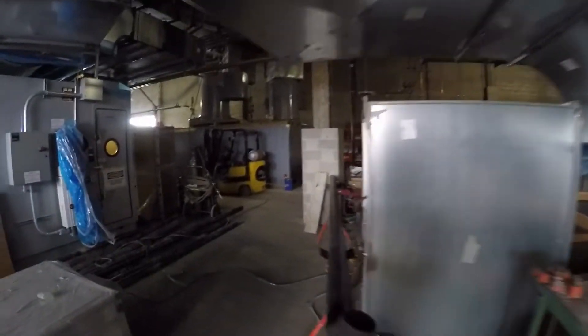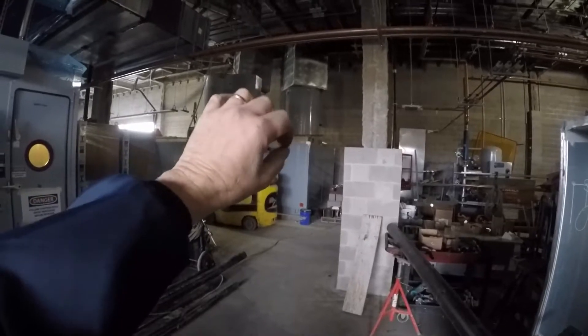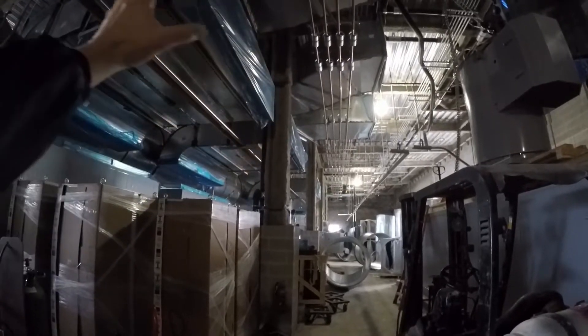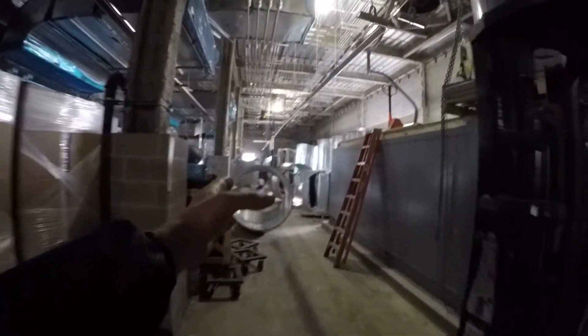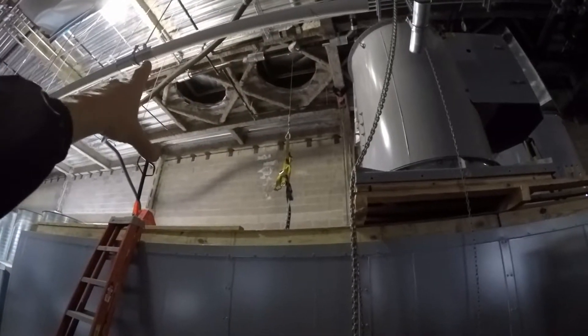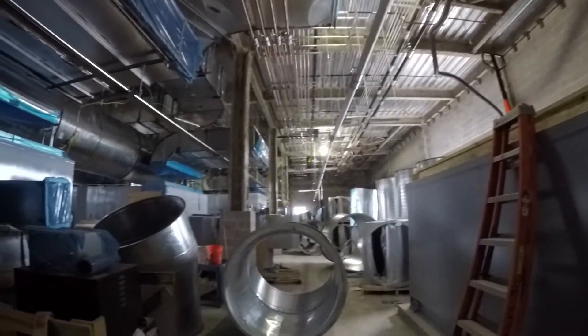We'll take a quick peek into the mechanical room — they're just in the process of building an exhaust fan room. The building has such an exhaust requirement it's going to have a special room for the exhaust fans. It's in the mid stages of rough-in. We can see the large ducts that are protected and covered right now; eventually those will all get tied in. This duct right here looks to be 50 inches across. Up through the roof, you can see the penetrations coming out of the exhaust room that are temporarily protected. This is the service area — this is what keeps the building going.